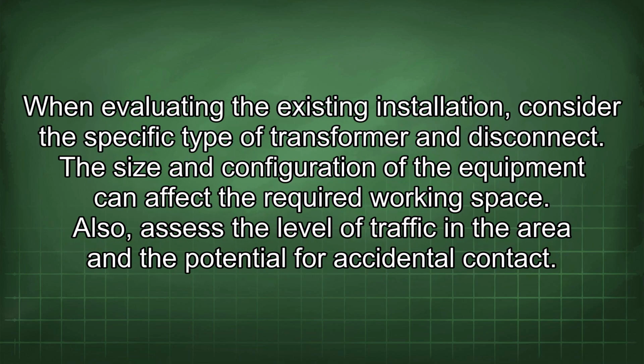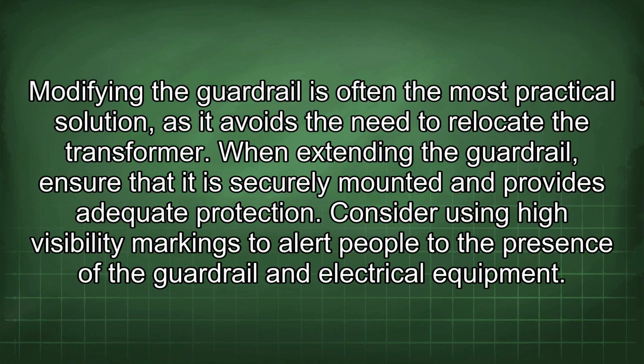When evaluating the existing installation, consider the specific type of transformer and disconnect. The size and configuration of the equipment can affect the required working space. Also, assess the level of traffic in the area and the potential for accidental contact. Modifying the guardrail is often the most practical solution, as it avoids the need to relocate the transformer. When extending the guardrail, ensure that it is securely mounted and provides adequate protection. Consider using high visibility markings to alert people to the presence of the guardrail and electrical equipment.